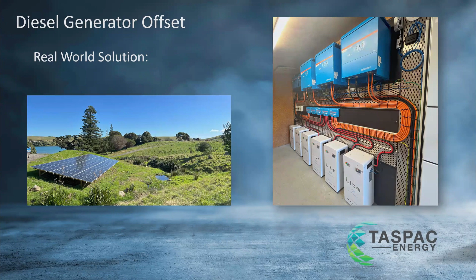There's the results: 19% diesel generator usage offset in the last 7 days. 22% in the last 24 hours, so they might have had some bad weather or a higher load. They're actually running at more than 80 kilowatt hours a day, now running about 95. That's always going to happen, you'll get creep in the load. The last 30 days, 14%. The last 365 days, they're down to 13% diesel generator usage as opposed to 100%.